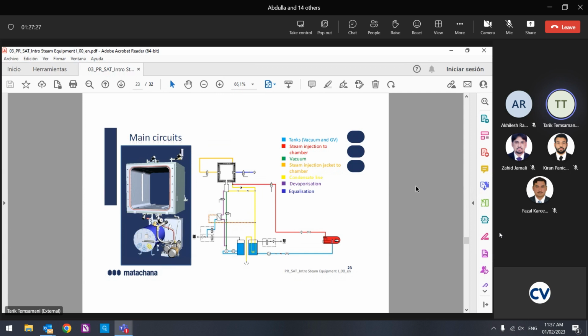Why do we do that? Why don't we put the steam directly to the chamber? You can do that. Why didn't we do that? To heat the chamber first, then steam injection. Maybe adjust the pressure in the chamber. It will not go directly moisture in the chamber. In our design, we put the steam in the jacket, so we reach the temperature faster.